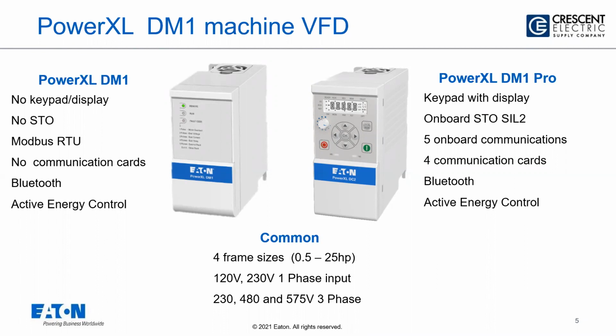And then we have another version of that has a keypad that's on it. And so you can program it, you can monitor it, you can run it all from the keypad. So from a functionality standpoint, they both do the same thing. They both can run induction motors or permanent magnet motors. They both have this wonderful algorithm called active energy control, which can save you between 2 and 10% energy savings on your variable torque loads, your pumps and fans.